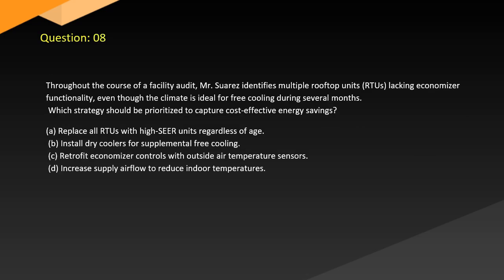Question 8. Throughout the course of a facility audit, an auditor identifies multiple rooftop units that lack economizer functionality, even though the climate is ideal for free cooling during several months. Which strategy should be prioritized to capture cost-effective energy savings? A. Replace all RTUs with high-efficiency units regardless of age. B. Install dry coolers for supplemental free cooling. C. Retrofit economizer controls with outside air temperature sensors. D. Increase supply airflow to reduce indoor temperatures.